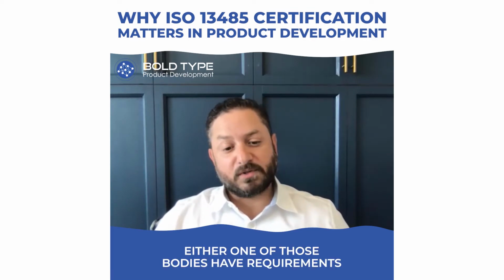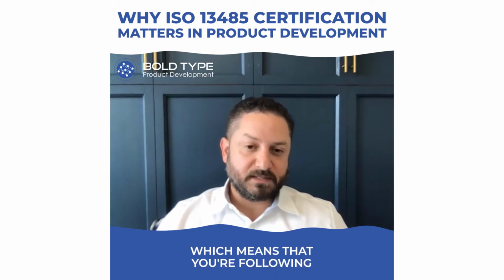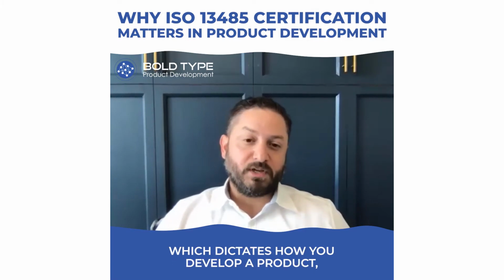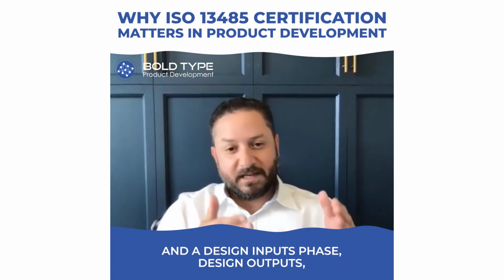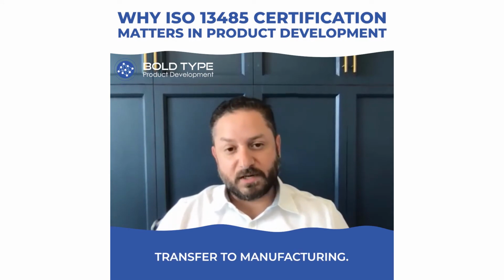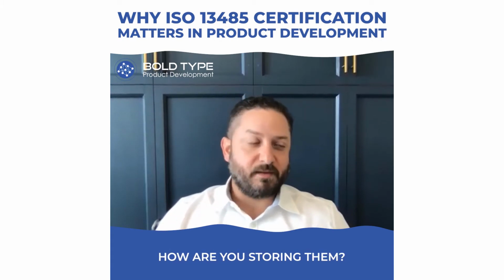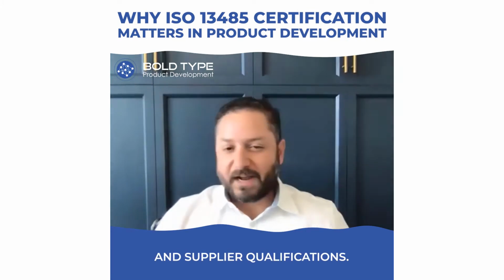Either one of those bodies have requirements around what they call a quality management system, which means that you're following certain processes and procedures in doing the things that you do. Anything from design controls, for example, which dictates how you develop a product, having various phases like a planning phase and a design inputs phase, design outputs, design verification, validation, transfer to manufacturing. They have certain guidelines that you're supposed to follow. Things like document control: how are you keeping records? How are you storing them? How are people signing off on documents? Those sorts of things. And supplier qualifications.